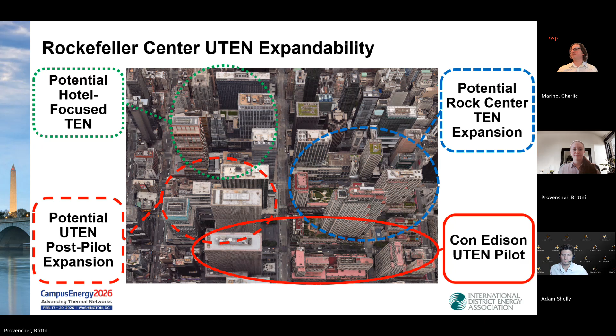While working with the central plant's operations team to generate utility-grade waste heat and minimize central plant impacts, it was agreed that its sequence of operations can be changed to prioritize the use of larger, different chillers during all heating hours. These larger chillers are currently used during high winter loads. This change was more palatable to the operations team than installing a new heat recovery chiller in the central plant, which would have required relocating existing equipment, retrofitting plant piping distribution, and modified controls. We didn't start designing the project with this change in mind, so it's useful to know this can be an option while modeling future UTENs.